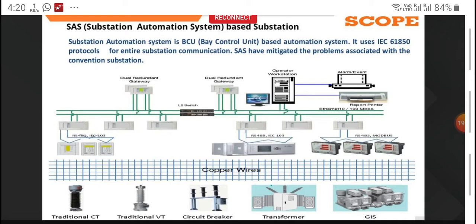So in this case, people are using a protocol converter, Modbus to 61850, and sending it on. Or some software or some SCADA systems already have the feature of taking different protocols in parallel. Like they take 103 as a protocol directly, there is no protocol conversion. There is 61850 also directly taken to the network, or Modbus also they can directly take to the network, and through the switches, with some media conversion, they take these things without protocol conversion. They take this data to the substation automation system.